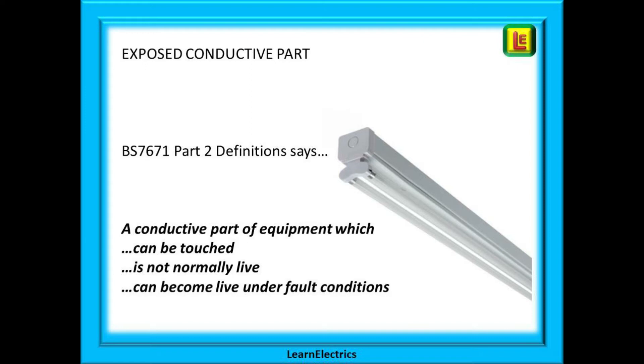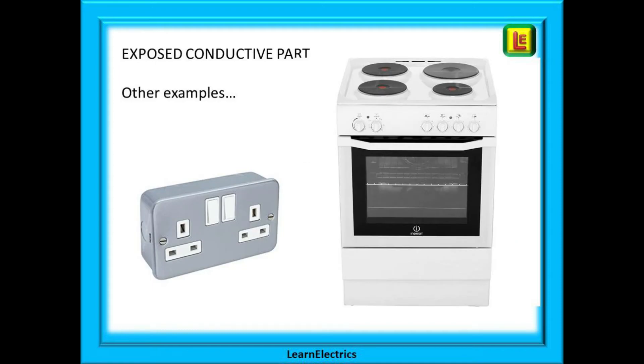If we start with exposed conductive parts, the definitions section tells us that these are conductive parts of electrical equipment which can be touched, are not normally live but can become live during an electrical fault. Here we have shown a fluorescent light fitting — the casing is made of metal so it is conductive. In normal fault-free conditions this casing is at zero volts and touching it will not give you an electric shock. But during a fault, let's say the live conductor works loose and touches the casing — until the fuse blows or the breaker trips, the casing will be at 230 volts. Touching it now is likely to give you an electric shock.